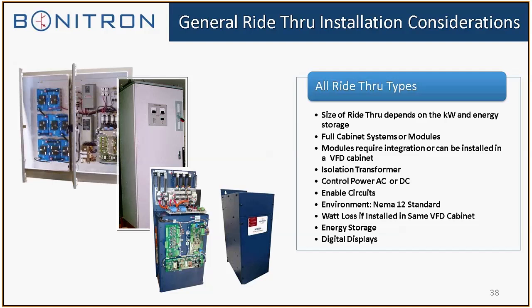But the ride-through voltage regulator booster and the other ride-through modules, the watt loss is about the same as the VFD, depending on the size of the VFD. So that could double the watt loss, but usually you're not past an allowable level even by using the ride-through, especially if you're using the single unit sag ride-through.